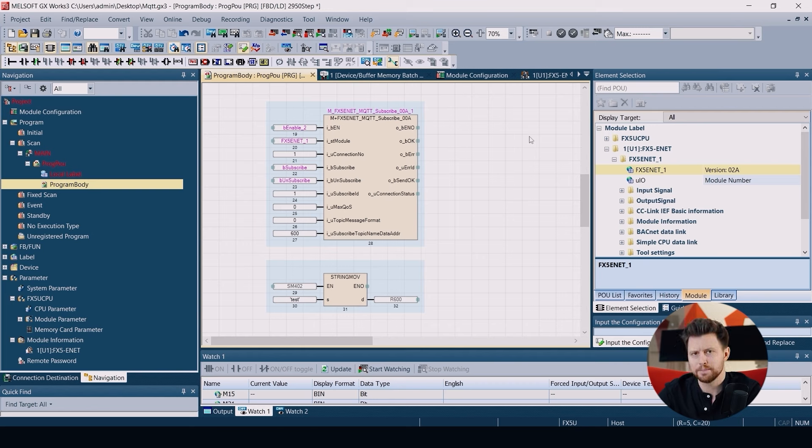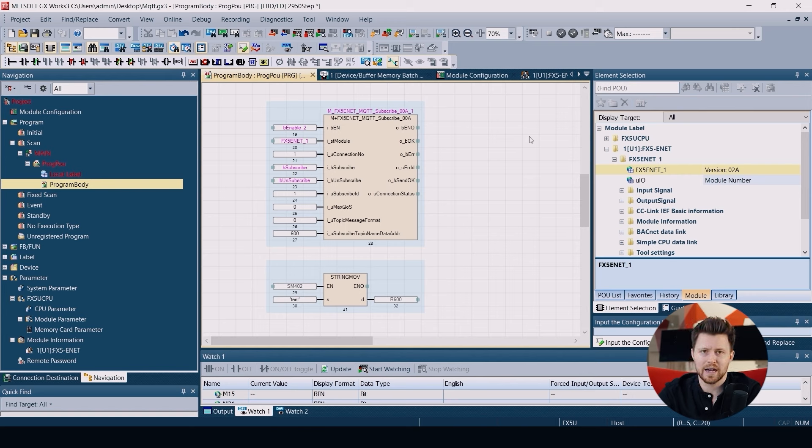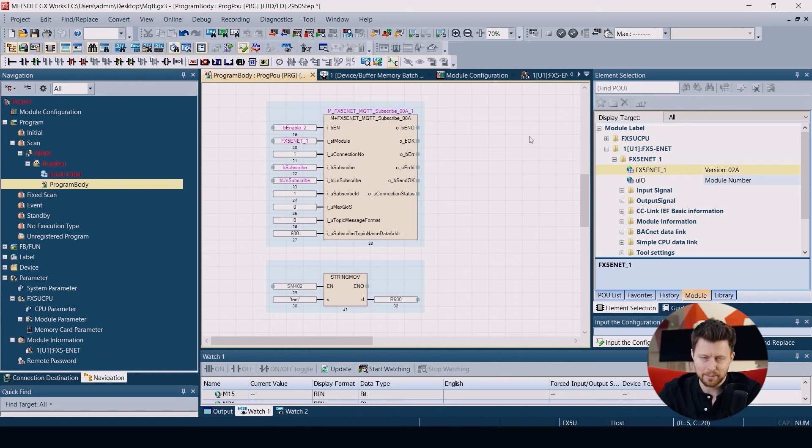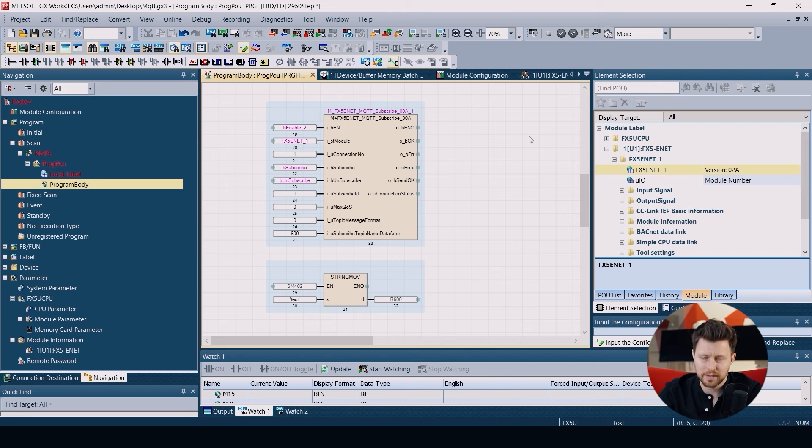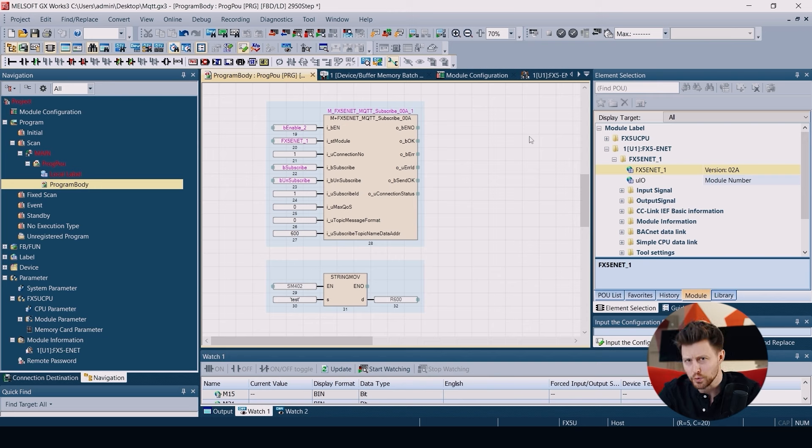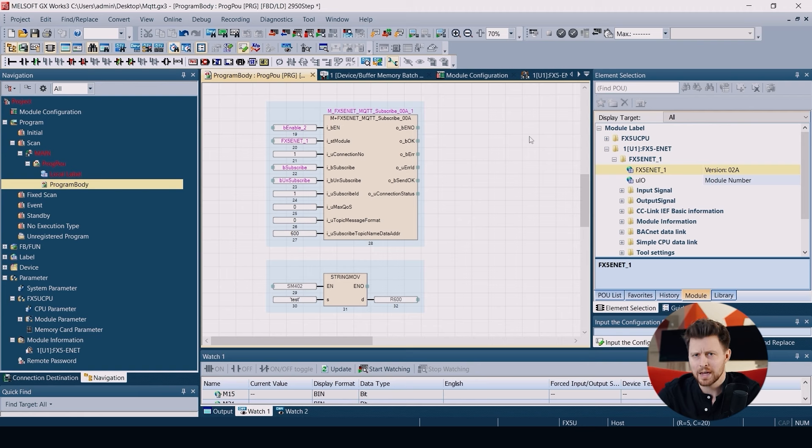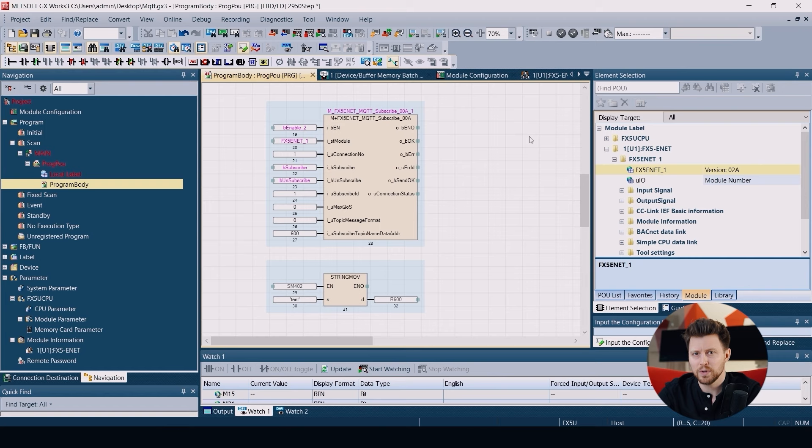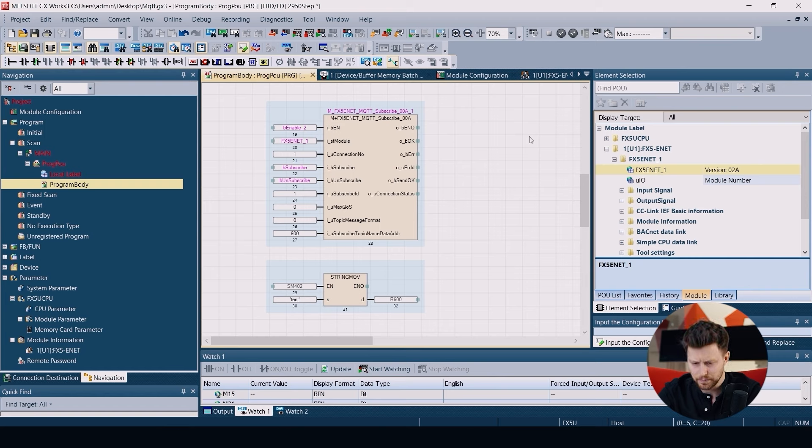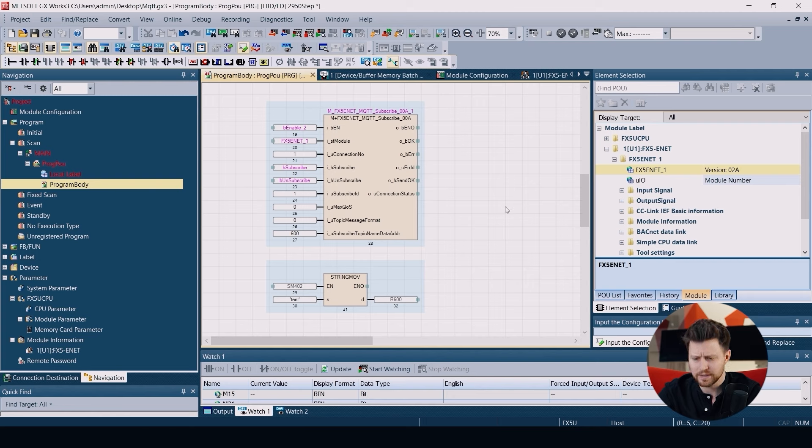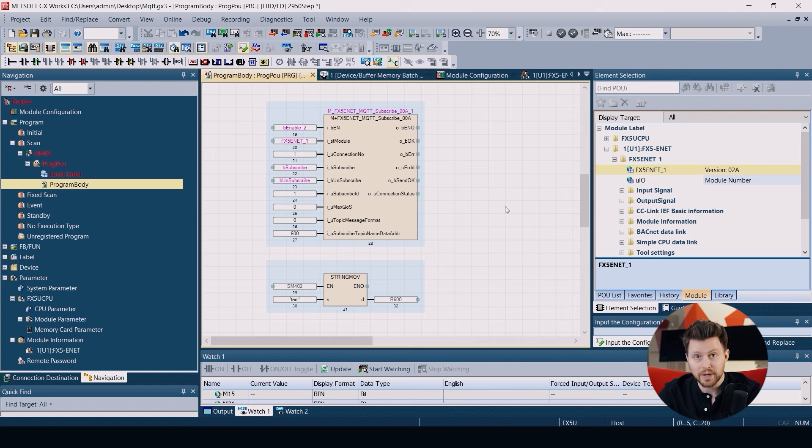This parameter controls the assurance of the message delivery. I'm not going to go into details today, but it can be 0, 1, or 2 in MQTT in general. But on FX5 Compact PLCs we can use only 0 or 1. I will choose 0 in my case. Then we have the message format. So I choose 0 again because we use ASCII codes.